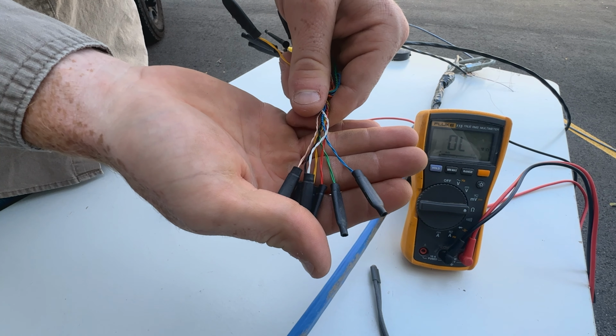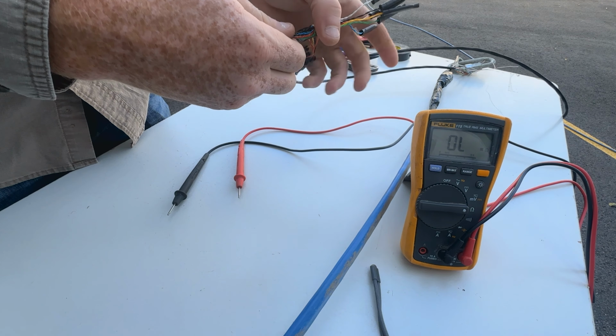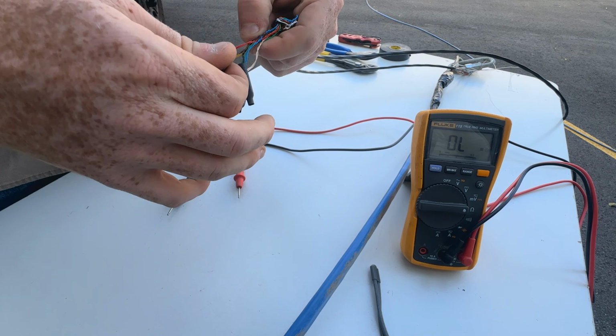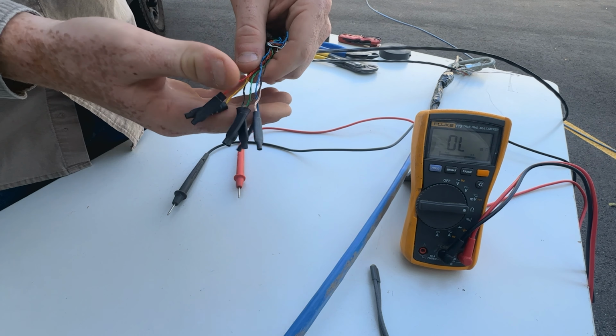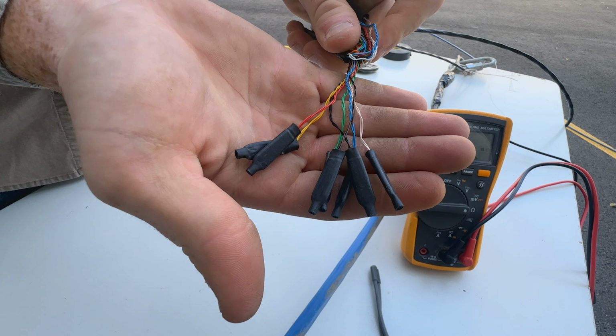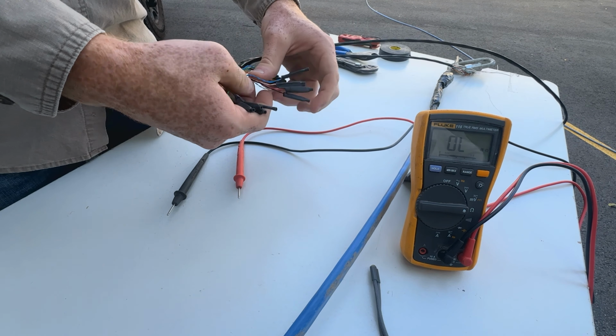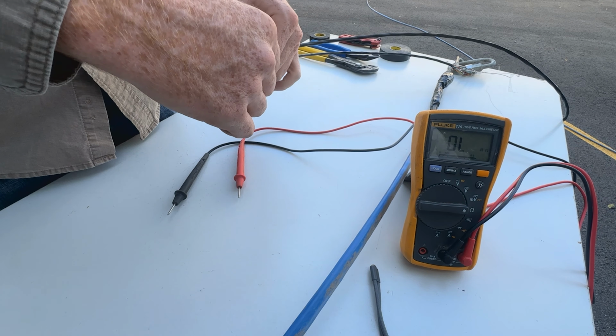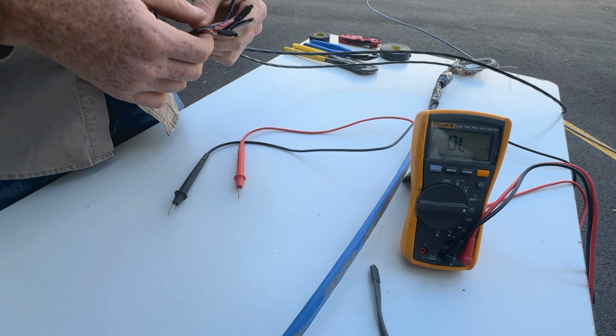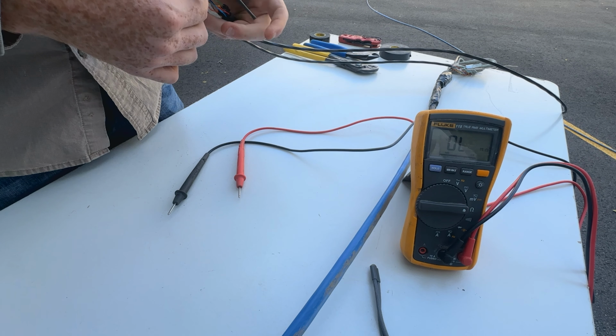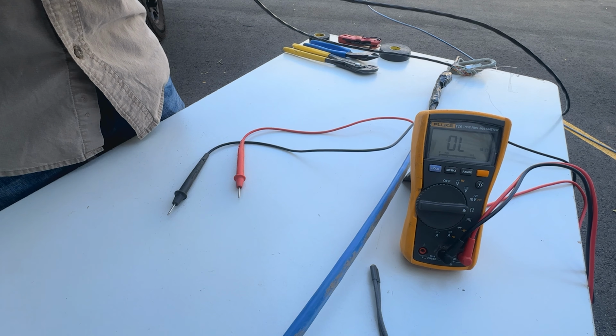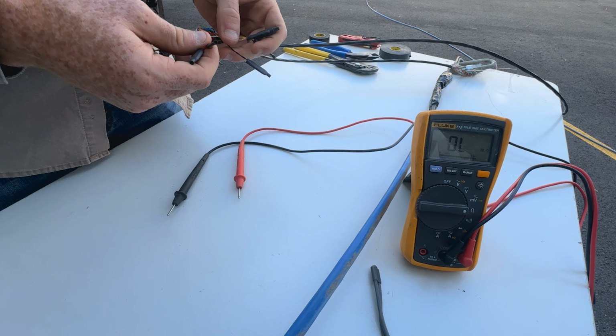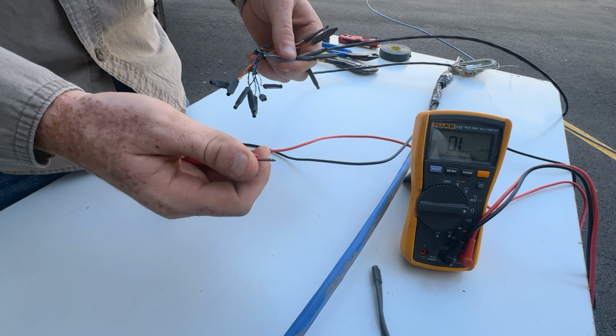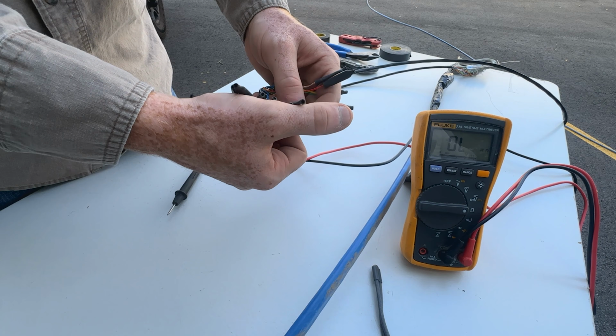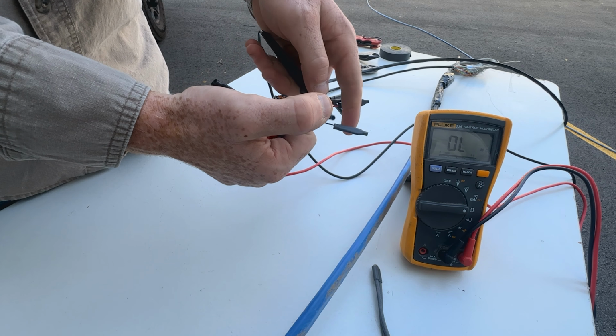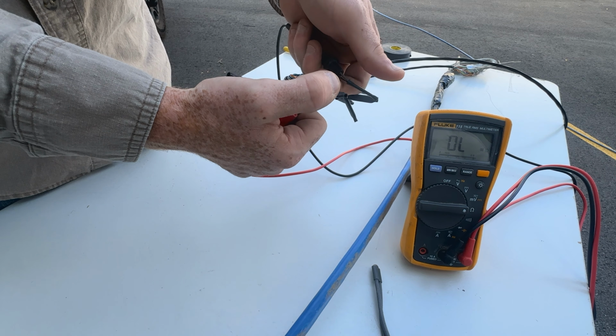This would be your white group. And finally, your brown group. We will begin with our white group since that's the bottom of the cable. Then we can work our way up. We will be pushing one of our probes on our multimeter into the crimp with the 2 white wires. The other probe on our multimeter will go into the crimp with the 2 black wires in the white group.